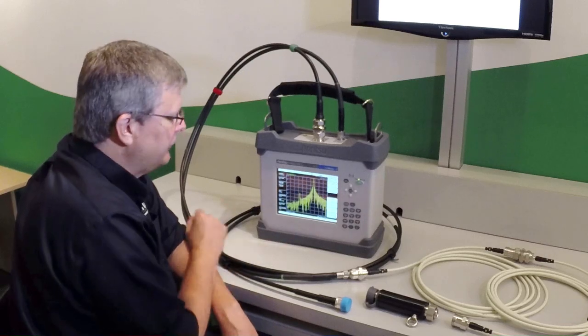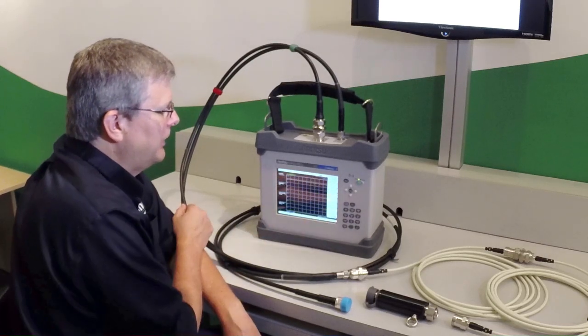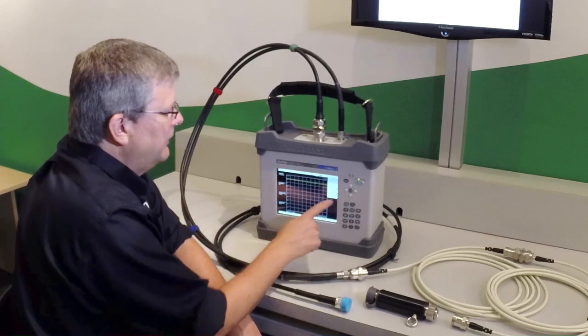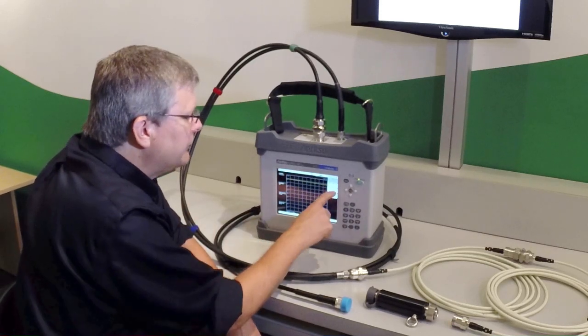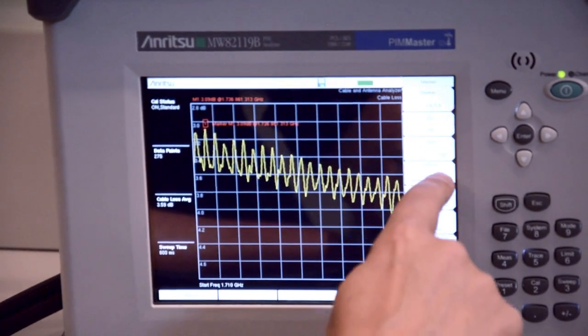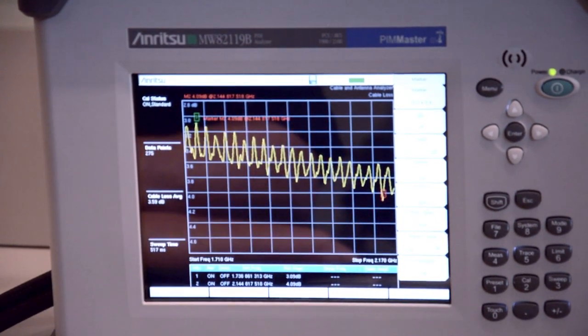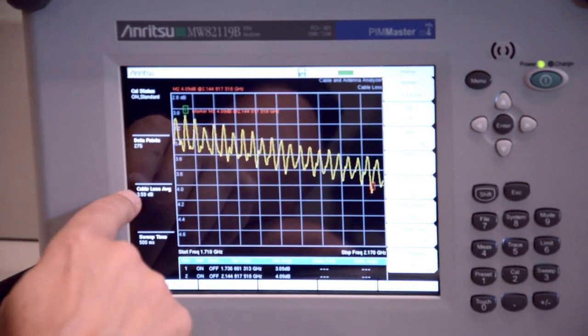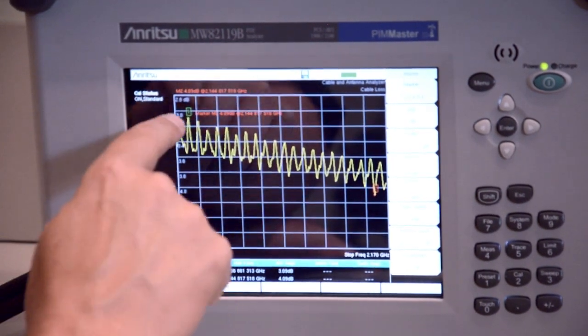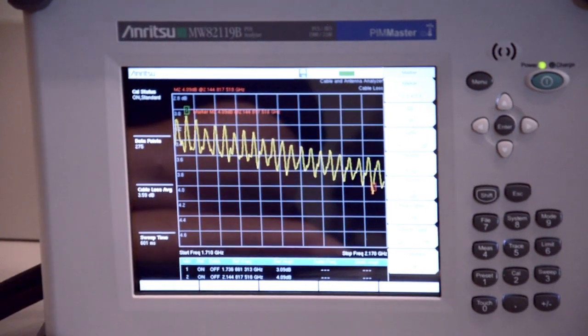While the cable is open, the next logical test to do is go into the measurements menu and perform a cable loss test. I'll do the amplitude to auto scale, and in the marker menu we have an automatic feature to automatically apply markers at the peak and the valley. It shows us here that the average cable loss is 3.59 dB, but I've also put markers at the peak and the valley in case someone wants to mathematically verify that measurement.